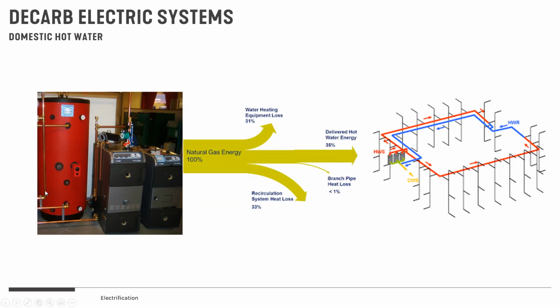When we look at how one of these systems is actually piped in a building, they've got this big system in the basement producing all this hot water. But in real life, there's quite a bit of loss coming from the actual system, and loss in all the piping going around your building, all the heat going out of the building. You lose about a third of the energy just in the piping. So by the time you've burned all this natural gas, you only end up getting about 35% of the heat delivered to your faucet—what you shower with, what you wash your hands with is only about 30% of the water you heated.